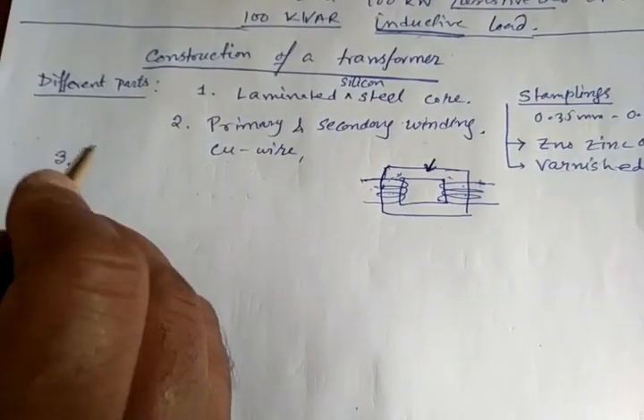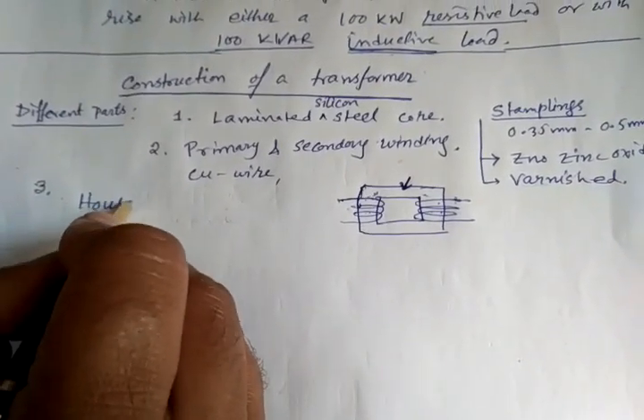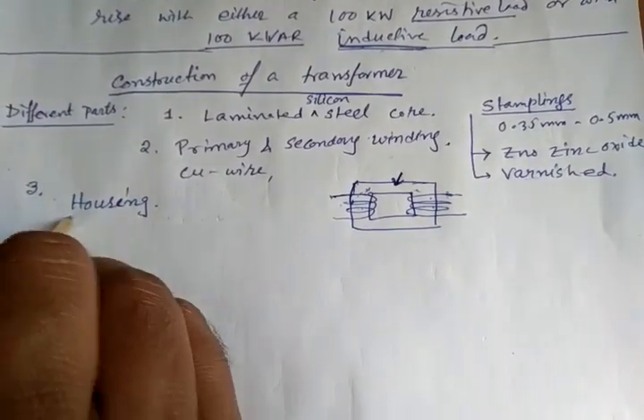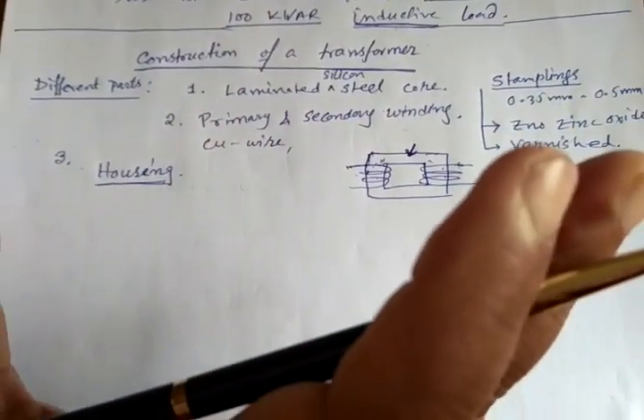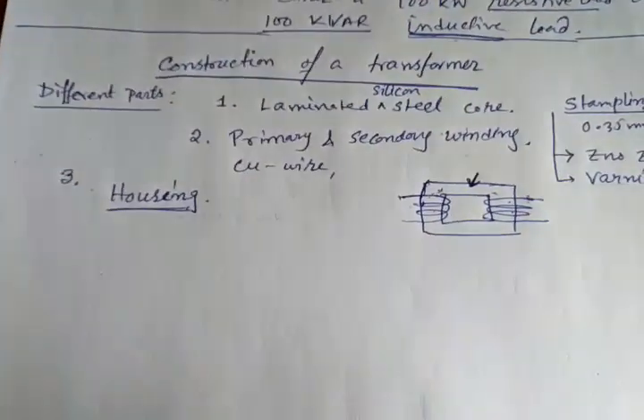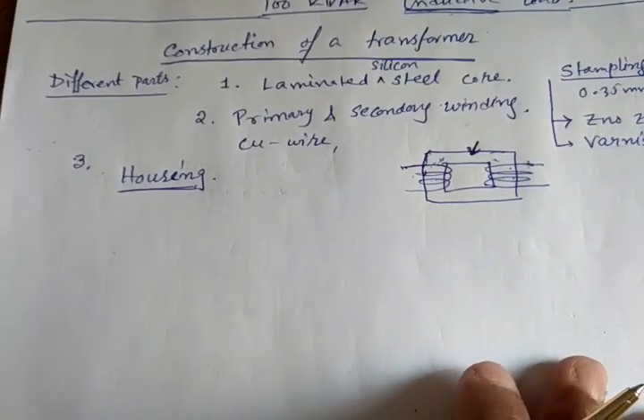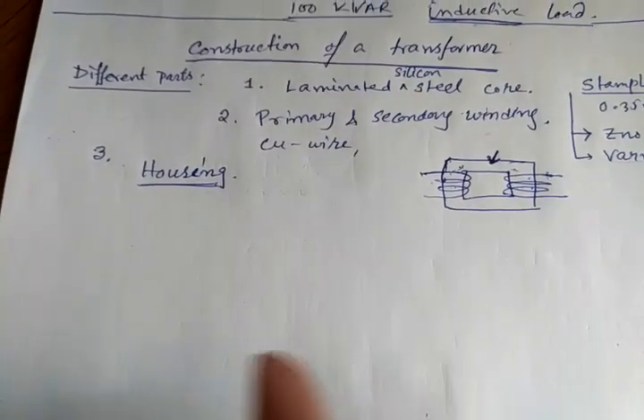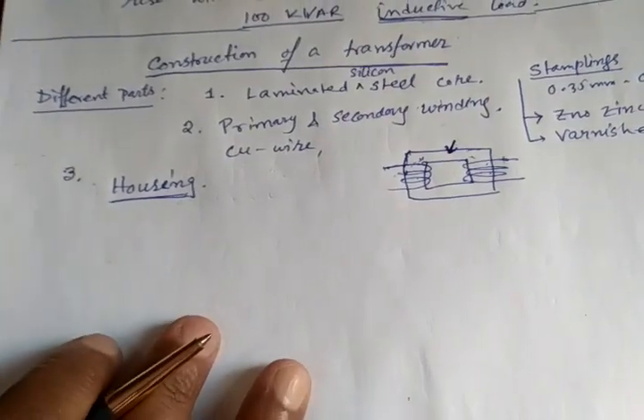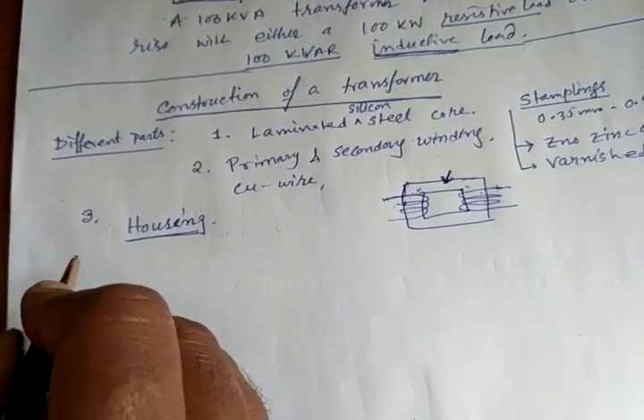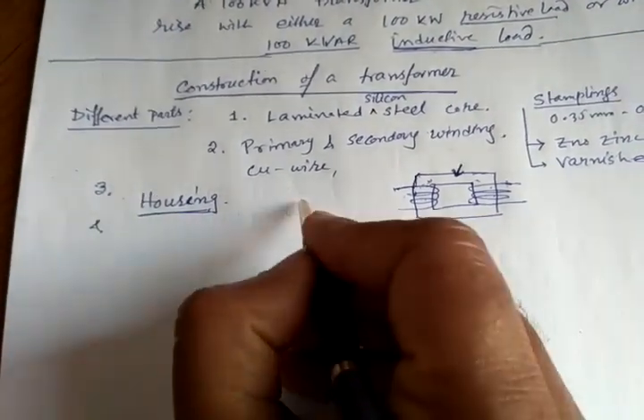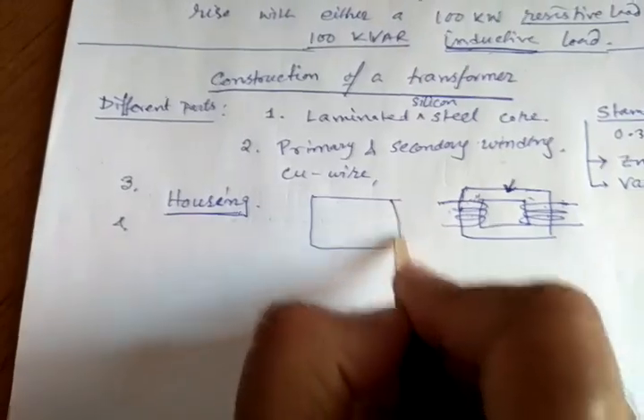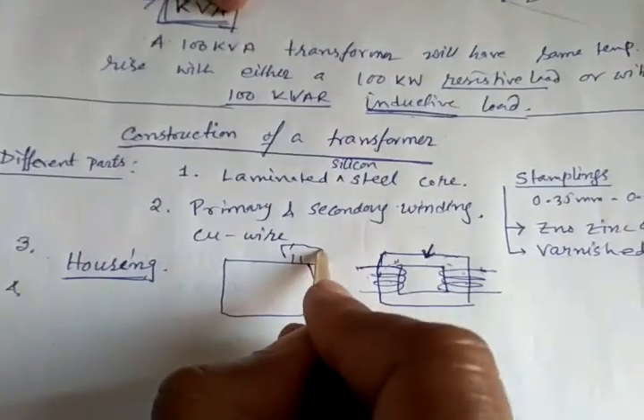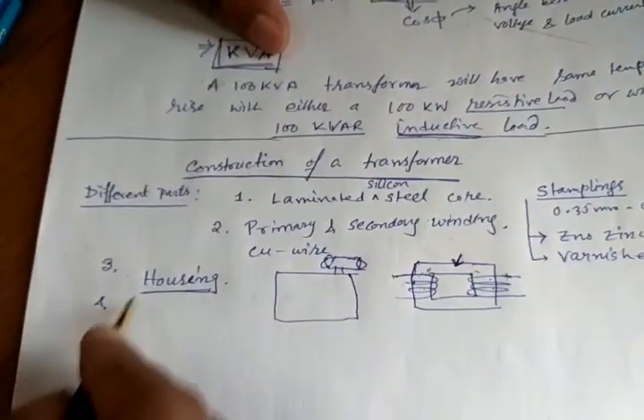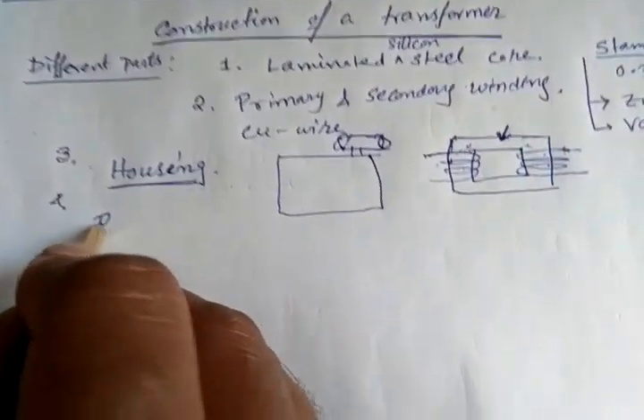Third part, we can say the housing. Basically, large transformers are housed in a big airtight tank, and there may be different types of cooling of transformer. Depending on that, there may be some transformer oil, or it may be air cooled, some blower, fan, etc. may be used. We'll discuss a bit about that. And this housing is basically the outer box, the tank. We'll see this later.